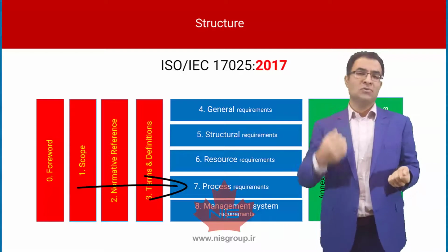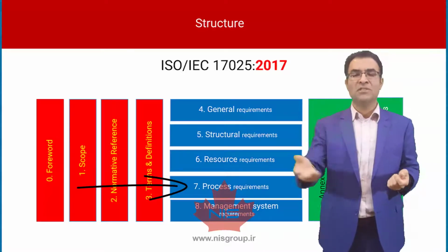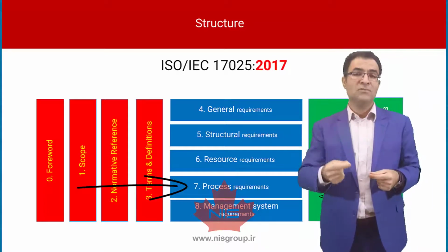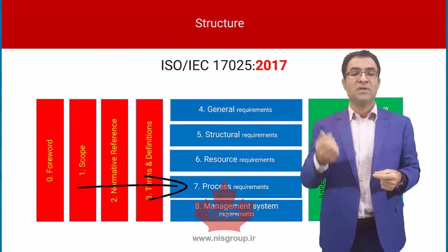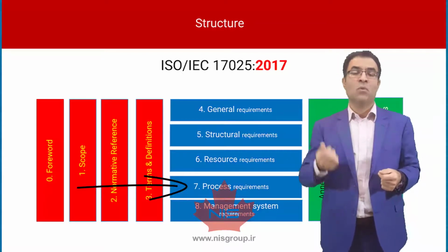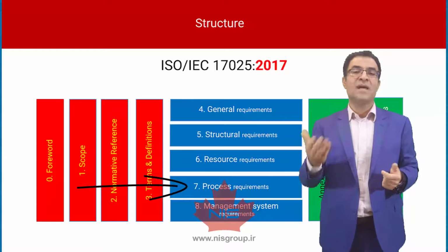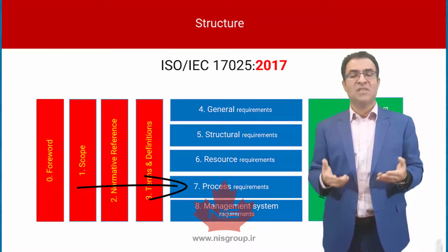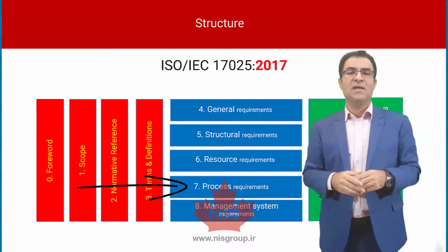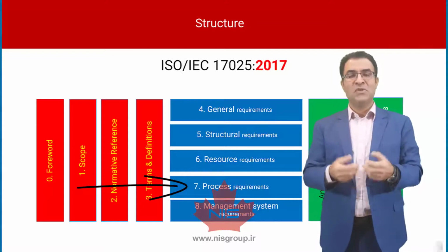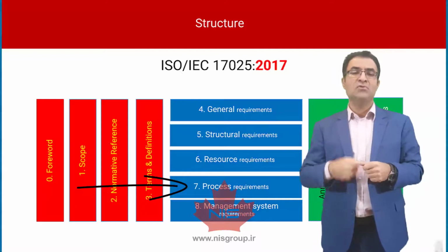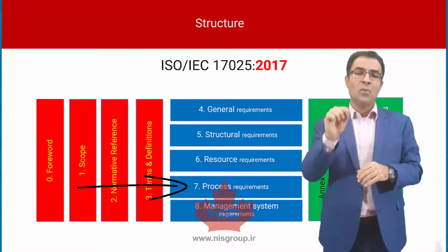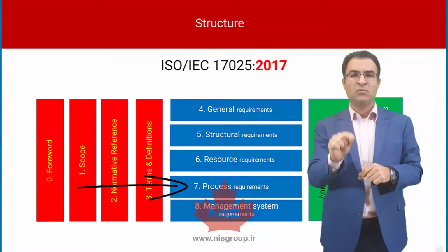Also, quality control departments or any other measuring or monitoring system or department that is using any measurement or monitoring instrument shall also refer to this kind of calibration laboratory. Why? To get their instrument calibrated. What is meant by calibration? Calibration means to identify the deviation between the true value and the readings. When you get your instrument calibrated, you receive a calibration report, and on that report it is written how much deviation your measurement instrument has.